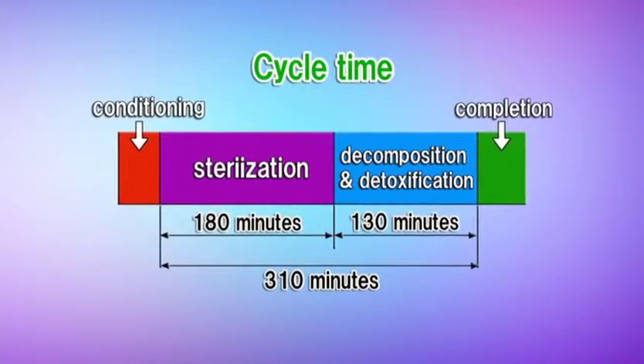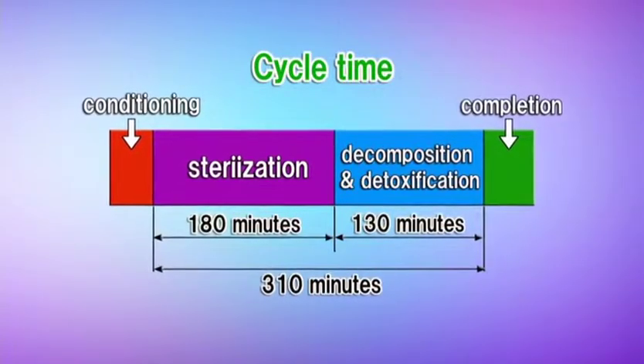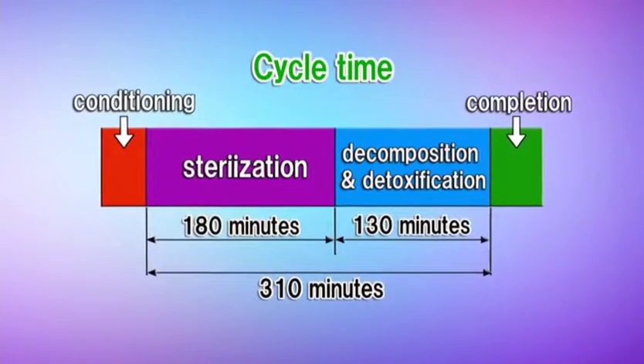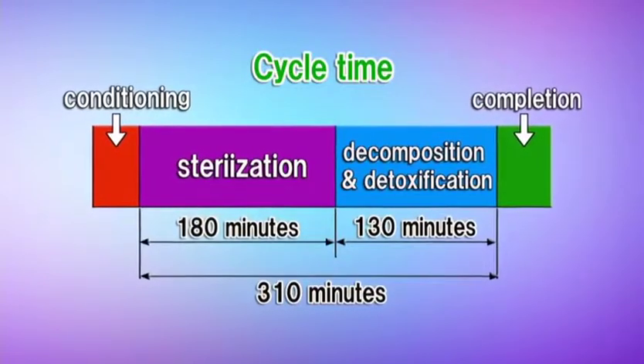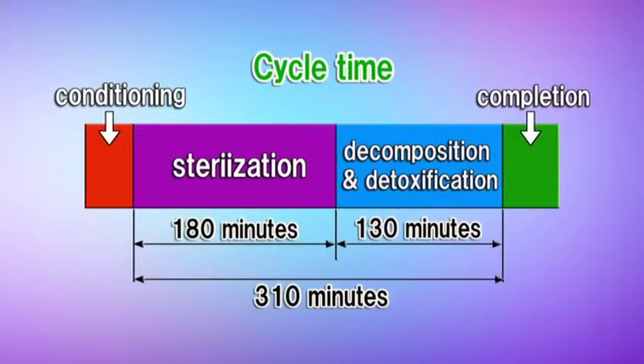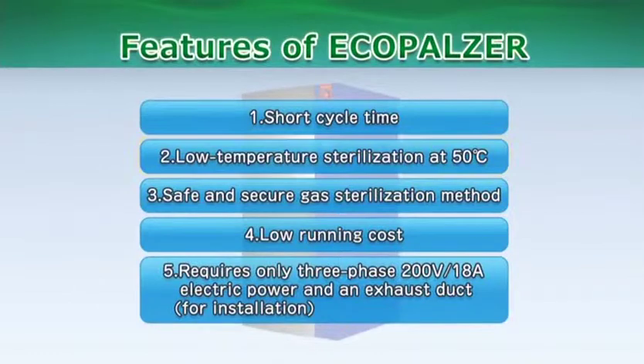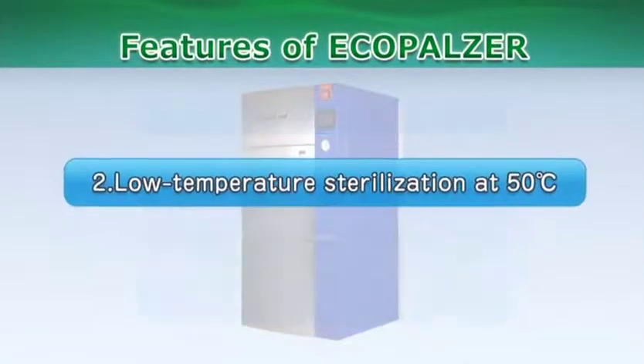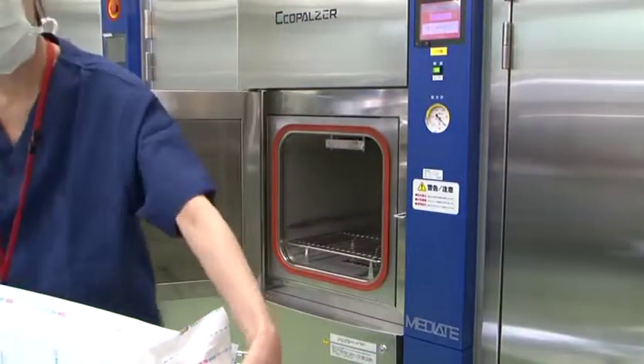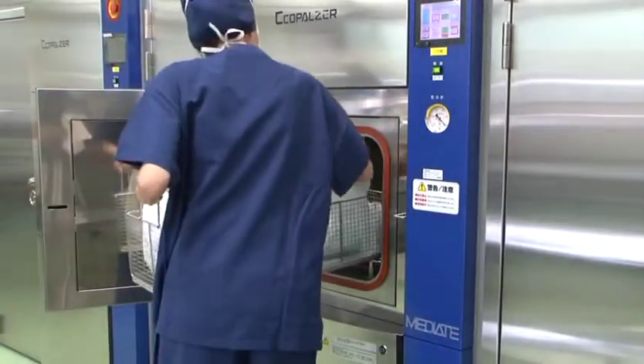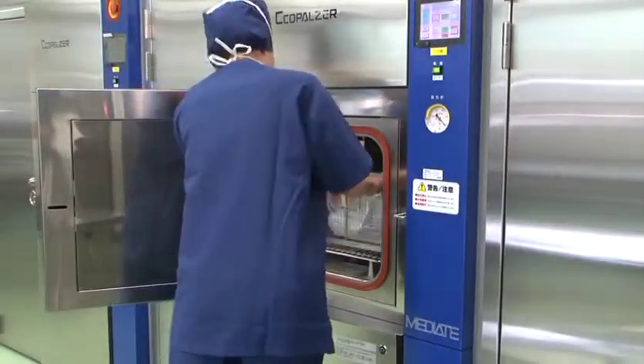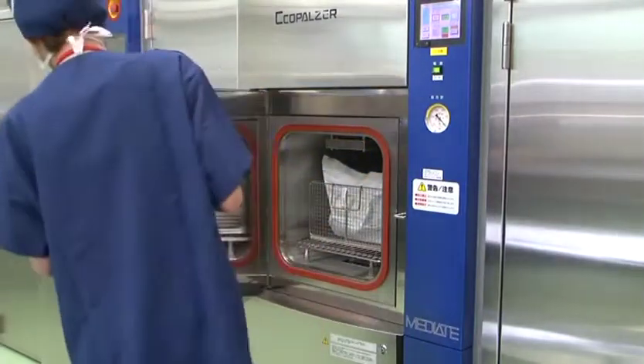With ECOPALZER, we have achieved a brief cycle time of 310 minutes per cycle, 180 minutes for sterilization, and 130 minutes for decomposition and detoxification. The entire process of sterilization is carried out at a low temperature of 50 degrees Celsius, so we can sterilize a wide range of heat-sensitive instruments, such as endoscopes and plastic objects. Medical instruments that were being sterilized with ethylene oxide gas can now be treated with our device in the same manner.